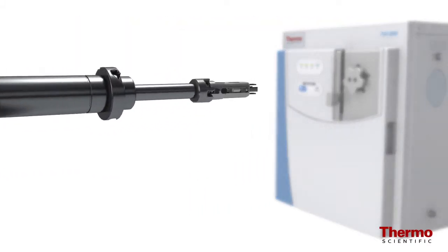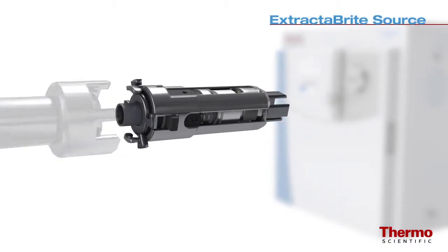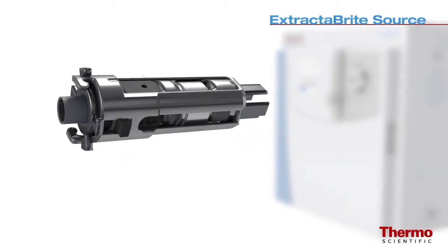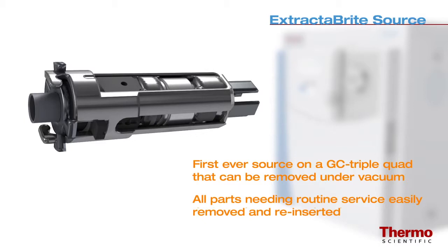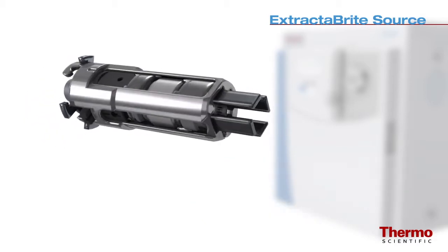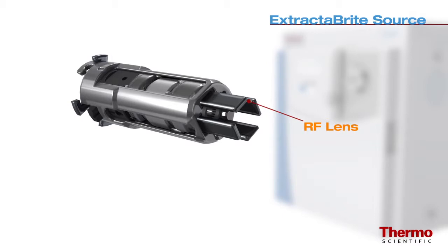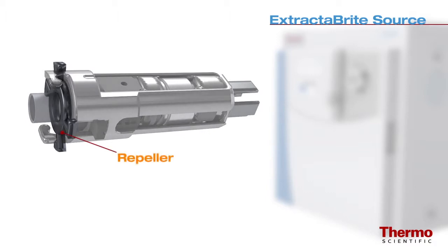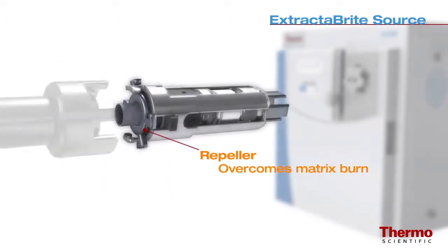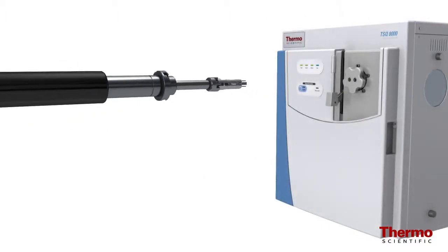The TSQ8000 system features the Thermo Scientific ExtractaBrite source cartridge — the first ever source on a GC triple quad that can be removed under vacuum. All parts that need routine service are contained in the source cartridge, including the patented RF lens, which protects the ion guide and quadrupoles from matrix buildup. The ExtractaBrite source also features a repeller designed to overcome matrix burn when it eventually forms.